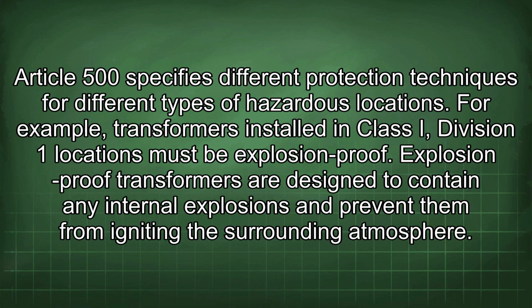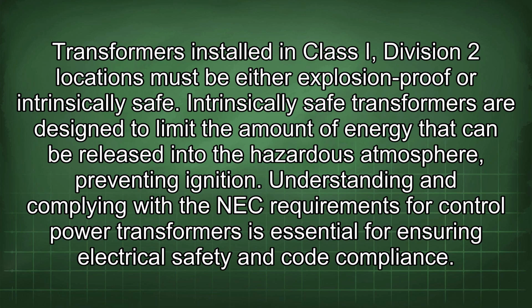Article 500 specifies different protection techniques for different types of hazardous locations. For example, transformers installed in Class I, Division 1 locations must be explosion-proof. Explosion-proof transformers are designed to contain any internal explosions and prevent them from igniting the surrounding atmosphere. Transformers installed in Class I, Division 2 locations must be either explosion-proof or intrinsically safe. Intrinsically safe transformers are designed to limit the amount of energy that can be released into the hazardous atmosphere, preventing ignition.